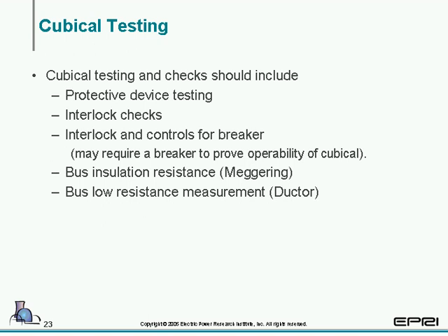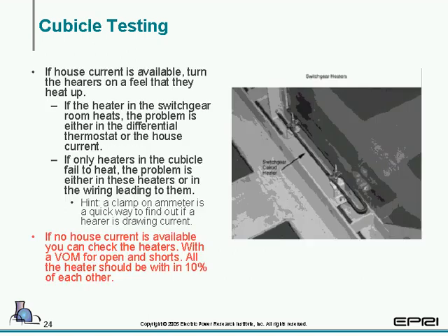After you get done cleaning, then you're going to want to test. Cubicles should be tested for the protective devices, the interlocks, and you can do insulation resistance measurement, and low resistance measurement (Ductor). And then you want to take a look and test the heaters, and we have several ways that you can test them. If house current is available, you can actually plug them in, turn them on, and see if they heat up. You may come across some that actually have thermostats, and you may have to adjust the thermostat up and down to verify if they work. If it does not have a thermostat, and you are unable to actually get to house current, you can use a volt ohm meter and look for opens and shorts in the wiring.